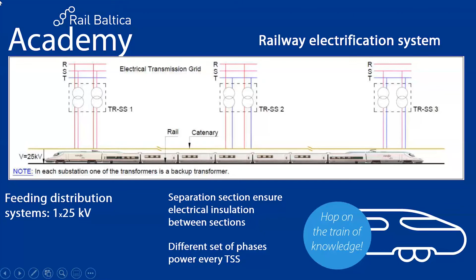Then we go to the 2x25 solution, which in principle is the one that will be implemented on Rail Baltica - the mainstream solution, subject to further detailed analysis. What's the difference? We can see in blue in the drawings that we have one additional feeder, called the negative feeder, which is added to the overhead catenary system.